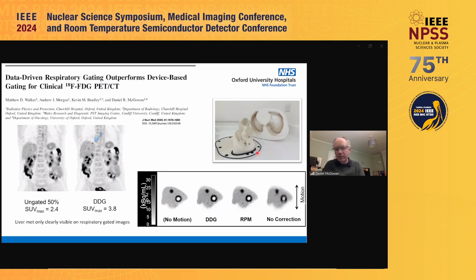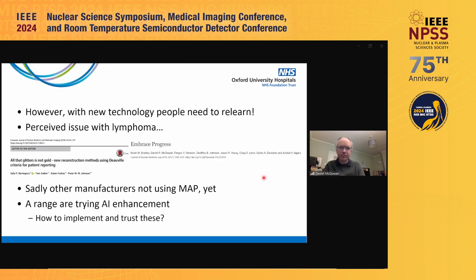And again, in this case, we used another phantom. However, here, unlike the image quality phantom, this was a 3D printed anthropomorphic phantom. This was actually a physicist's liver. So we did an MRI of a physicist, then printed their phantom. This was actually used for SIRT, Y90 optimization, but we also applied it here for F18. So you see the sort of images we get, which are more human-like, so you're able to see lesions or necrotic lesions with a cold central spot and see the impact of this algorithm. And again, it helps having this phantom and clinical view of things in order to get these things implemented in the clinic and persuade people of the value of this technology.